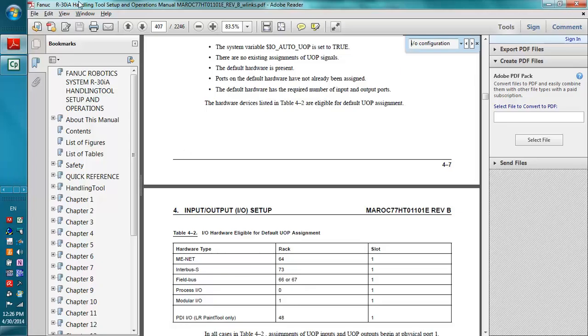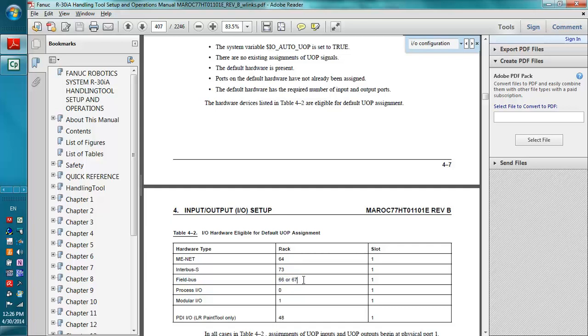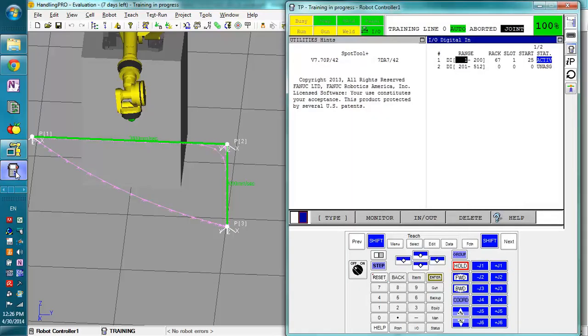You can find this in the Handling Tools Setup and Operations manual, but field bus is using rack 66 and 67, depending on whether you're dealing with the master side or slave side. Now, if you want to add extra digital inputs and outputs, you can. It's not so hard.